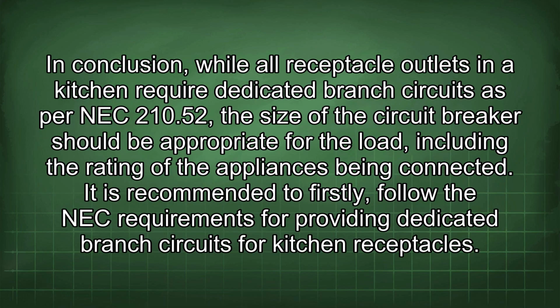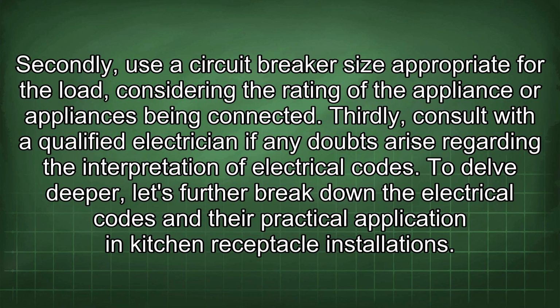In conclusion, while all receptacle outlets in a kitchen require dedicated branch circuits as per NEC 210.52, the size of the circuit breaker should be appropriate for the load, including the rating of the appliances being connected. It is recommended to firstly follow the NEC requirements for providing dedicated branch circuits for kitchen receptacles. Secondly, use a circuit breaker size appropriate for the load, considering the rating of the appliance or appliances being connected. Thirdly, consult with a qualified electrician if any doubts arise regarding the interpretation of electrical codes.